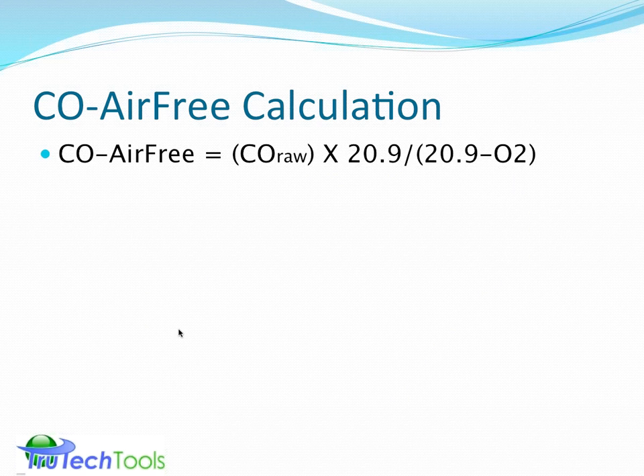So the calculation is here. It's basic science that the combustion analyzer is using. That's the CO raw. That's the number that's measured by the sensor. 20.9 comes in there because that's the standard concentration of oxygen in the atmosphere, and the O2 reading that's coming from your O2 sensor. So from this, you can very quickly derive that in order to make a CO air-free calculation, you must have a CO sensor and an oxygen sensor, which means a product that only has a CO sensor in it would not be suitable for CO air-free calculation.